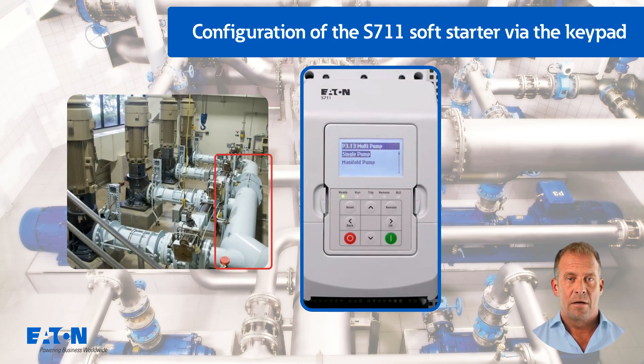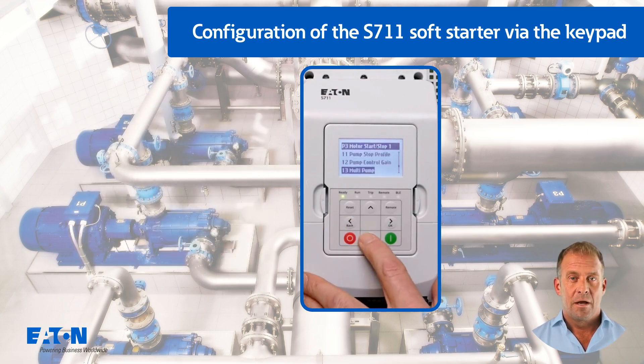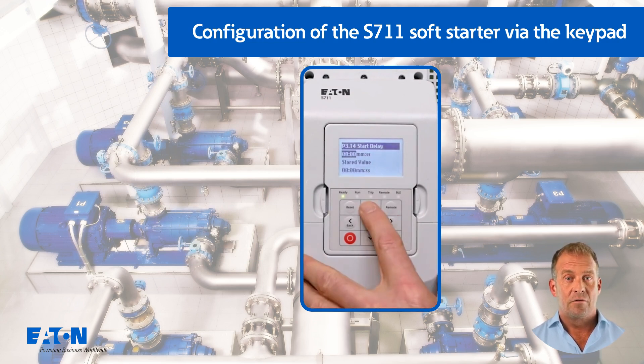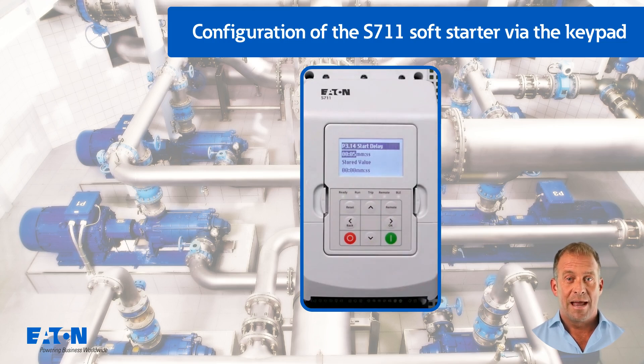this can be deactivated via parameter P3.13. The last parameter of interest for a pump application in this group is P3.14 start delay. With this parameter, the S711 carries out a delayed start.